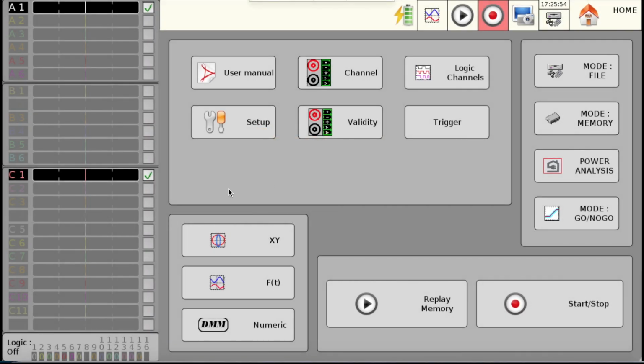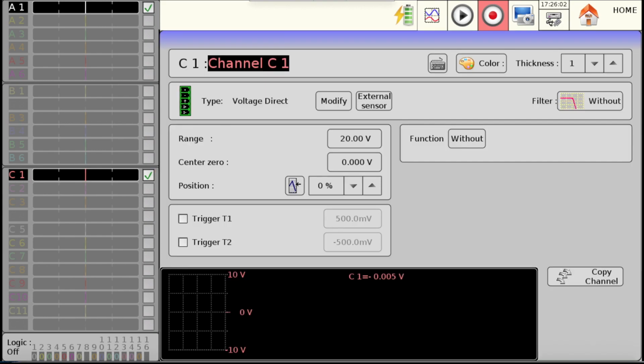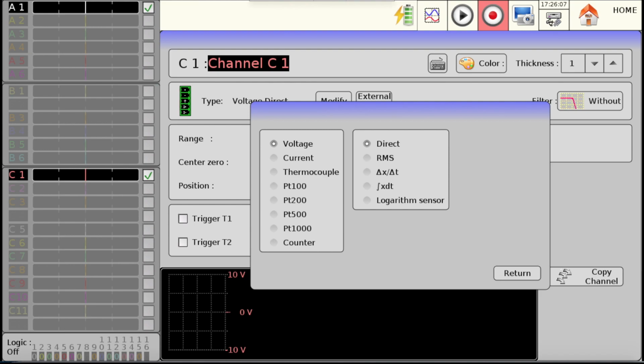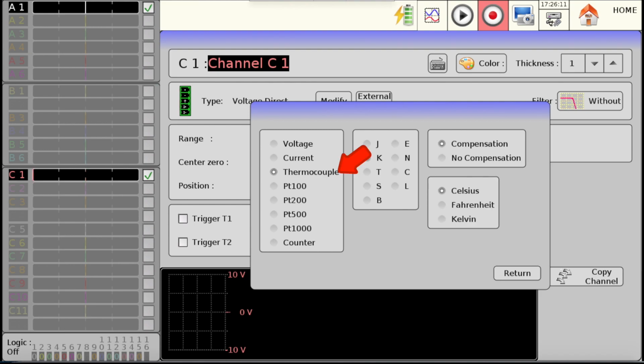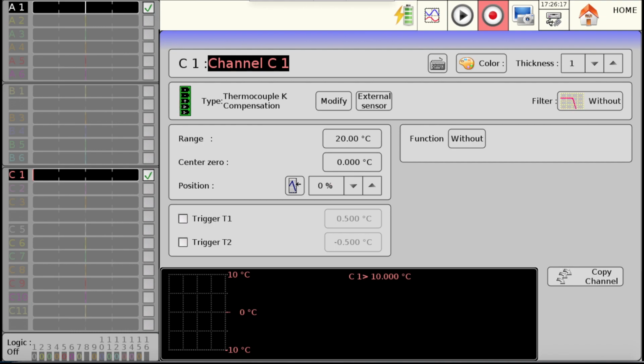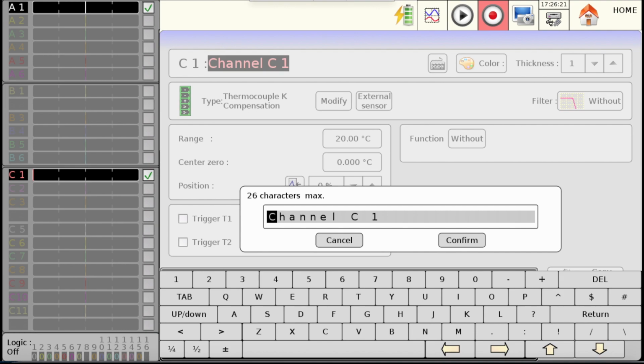Let's see together how to configure a channel. Select the desired channel and access the channel parameters by clicking on it. Define the type of signal you want to record. In our example, we will record a thermocouple, type K, and compensated, with a unit in degrees Celsius. Name the channel. In our case, it will be temperature.